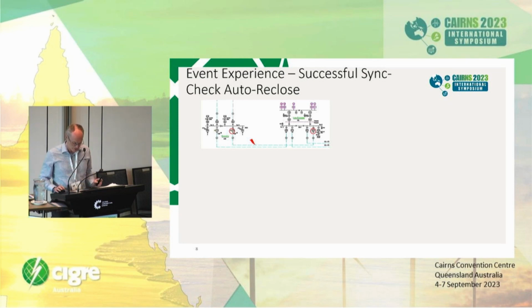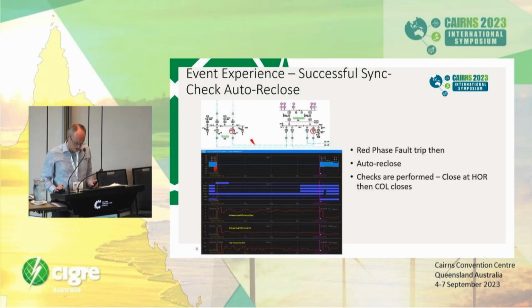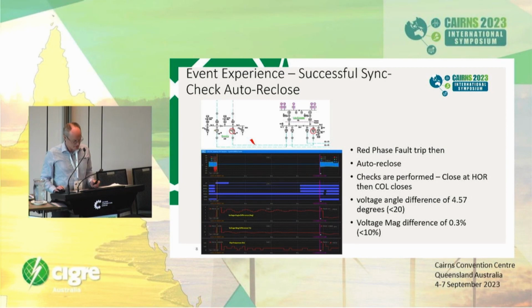The synchrophasor synchronism check scheme has now been implemented at a number of sites. There have been a number of successful operations where synchronism check has allowed auto-reclose to restore the circuit. One such case is illustrated in the slide for the Corridge to Hororata circuit, where there is a weak circuit to Corridge and the west coast with some local hydro generation. A red phase fault occurred, then the circuit auto-reclosed after checks showed small and allowable voltage angle difference, voltage magnitude difference, and zero slip frequency.